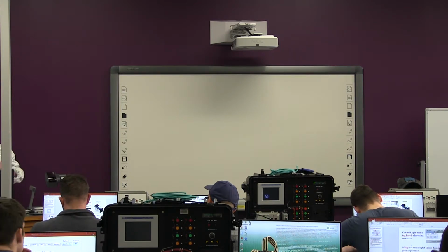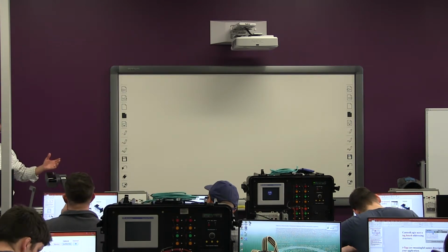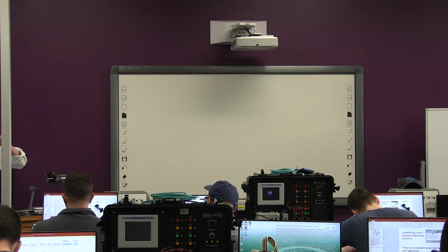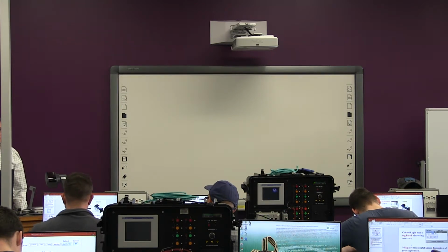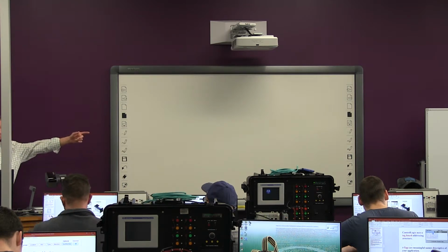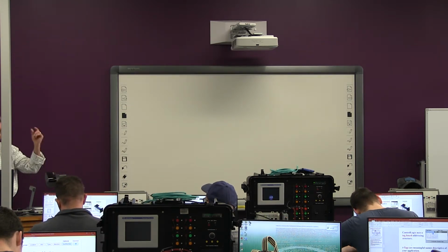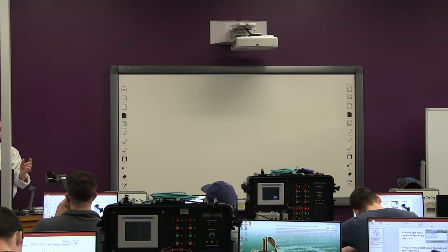They're on a network, and we set up produced and consumed tags to send and receive data. So if we're going to send some data over to that PLC, this PLC would have a produced tag in it called my tag. The other PLC that's receiving it will have a consumed tag called my tag. It has to have the same tag name. That way you can pass bits back and forth. Does that make sense? Maybe some kind of interlock.